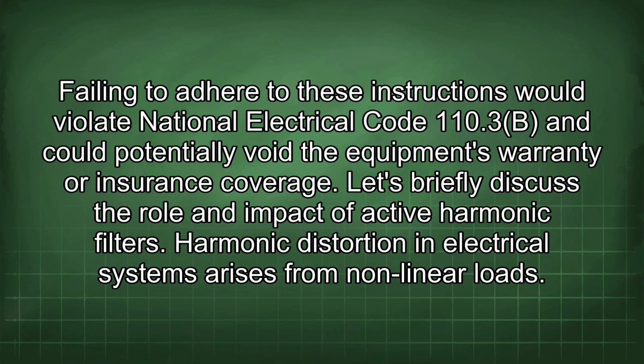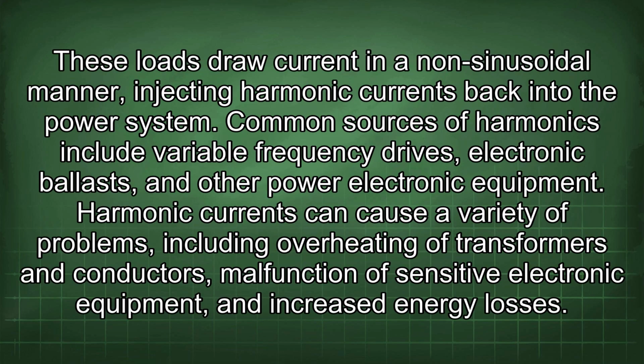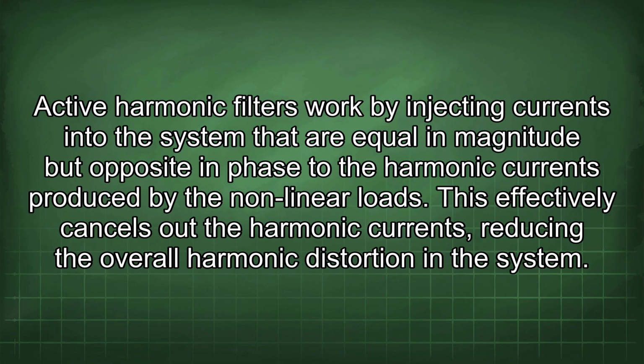Harmonic distortion in electrical systems arises from nonlinear loads. These loads draw current in a non-sinusoidal manner, injecting harmonic currents back into the power system. Common sources of harmonics include variable frequency drives, electronic ballasts, and other power electronic equipment. Harmonic currents can cause a variety of problems, including overheating of transformers and conductors, malfunction of sensitive electronic equipment, and increased energy losses. Active harmonic filters work by injecting currents into the system that are equal in magnitude but opposite in phase to the harmonic currents produced by the nonlinear loads. This effectively cancels out the harmonic currents, reducing the overall harmonic distortion in the system.